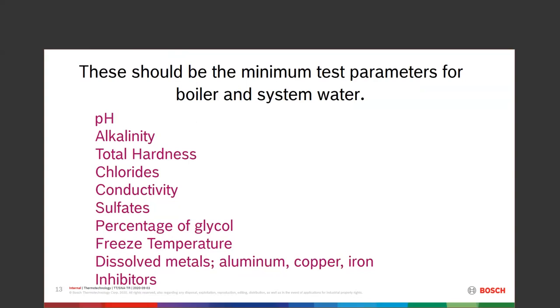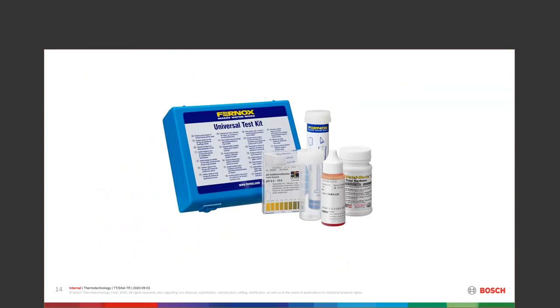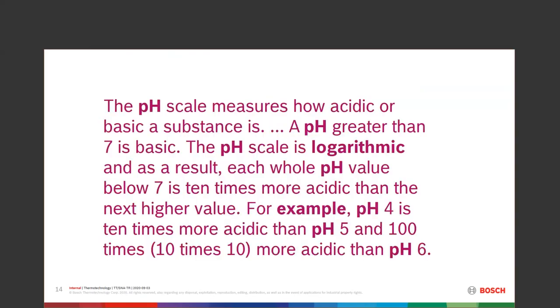If we treat the water coming in, it becomes less of an issue, because we treat the closed loop system once we have it tightened up. A universal test kit — Fernox makes one, Romar makes one — can test for pH with strips, total hardness, chlorides, conductivity, and more. We use Fernox a lot and recommend it with our Green Star boiler line. These kits are reasonably inexpensive and most anybody can run them.